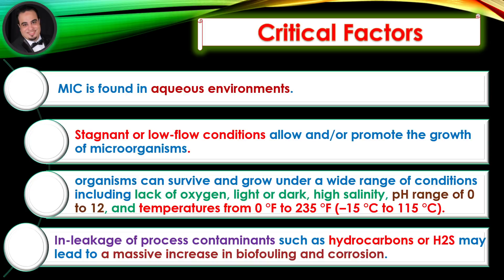Organisms can survive and grow under a wide range of conditions including lack of oxygen, light or dark, high salinity, pH range of 0 to 12, and temperatures from 0 degrees Fahrenheit to 235 degrees Fahrenheit. In-leakage of process contaminants such as hydrocarbons or hydrogen sulfide may lead to a massive increase in biofouling and corrosion.